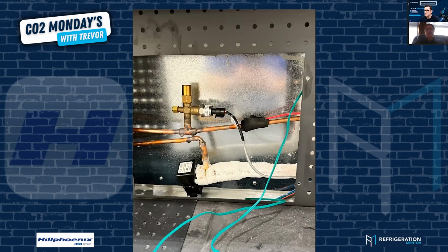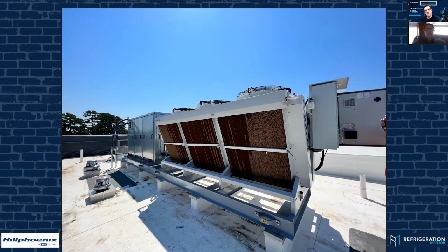And these are easy to put back. These are easy. You just take off the top panel up there. There's two. There's one on the top, one on the bottom. In the middle, you take those off, and that whole panel will just lift right up and come off. And then these bars on the outsides, you loosen them up and they flip out and allow the panels to drop out. You take your directional panel out, then you can pull the bottom ones out. Remember the order you take them out and put them back in. Yeah. That's very important. Yep.